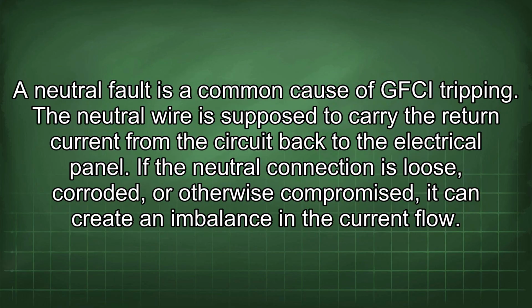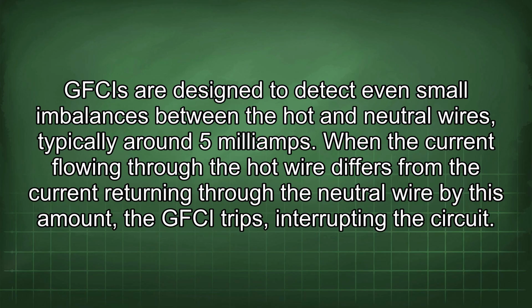A neutral fault is a common cause of GFCI tripping. The neutral wire is supposed to carry the return current from the circuit back to the electrical panel. If the neutral connection is loose, corroded, or otherwise compromised, it can create an imbalance in the current flow. GFCIs are designed to detect even small imbalances between the hot and neutral wires, typically around 5 mA. When the current flowing through the hot wire differs from the current returning through the neutral wire by this amount, the GFCI trips, interrupting the circuit.